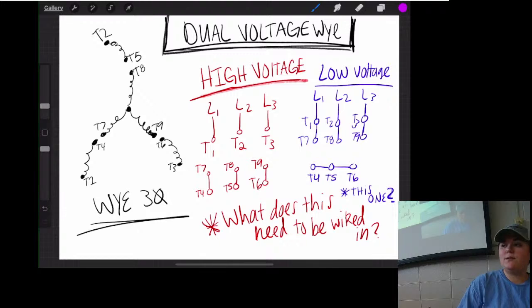That's why you want to choose the higher voltage - the book tells you the motor uses the same amount of power and gives the same horsepower output for either high or low voltage. But as the voltage is doubled, say from 240 to 480, or in the book's case 230 to 460, the current is cut in half. Using a reduced current enables the use of a smaller wire size, which reduces the cost of installation.